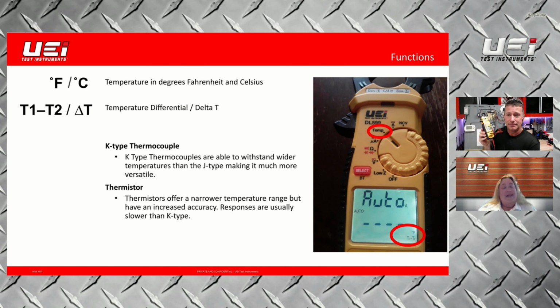The other thing I always like to caution people about—it's really hard to do, and you seem to get it right on the first try—is making sure you have your polarity right with thermocouples. You have two prongs: a wider prong and a narrower prong, and it coordinates just like an electrical outlet. If you've ever tried to plug in an appliance upside down, it's really hard to plug in. Occasionally somebody is able to make that happen, but making sure our polarity is right—the wider prong goes into the wider side and the narrow into the narrow.